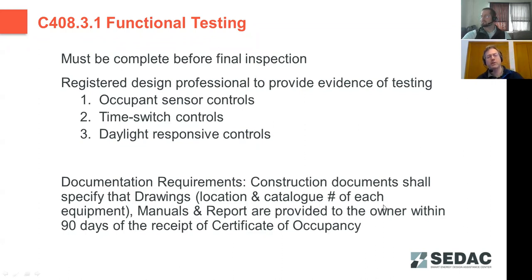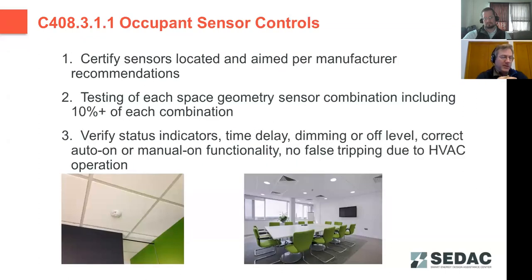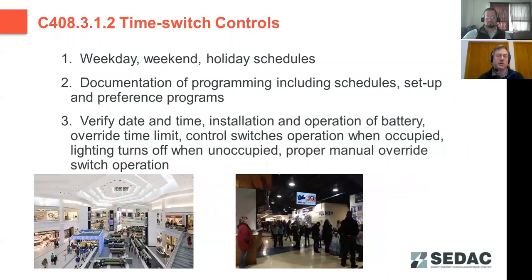So moving on to what we need to be testing in occupant sensor controls. We have to be testing every space geometry and sensor combination. So it's not uncommon that this is going to be requiring testing of nearly every space, because of different geometries. You might have two conference rooms that are mirror images of one another. That's still a difference of geometry. Where you might be able to do more sampling is if you have, say, a stack building where every floor is the same. It does go through several different things that have to be verified for each sensor location. Time switches are a little easier to do, as there you're testing the programming and verifying that the schedule is in there.